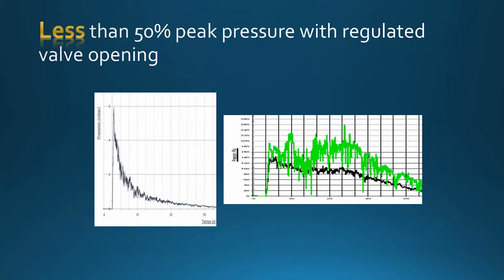So pressure regulating valves are only for inert agents. Currently, pretty much all of the inert agent manufacturers are coming up with some kind of pressure regulating valve, and our checks of those valves show us that they all pretty much perform in a similar fashion. So I'm just going to bring up a test here and show you what that looks like.